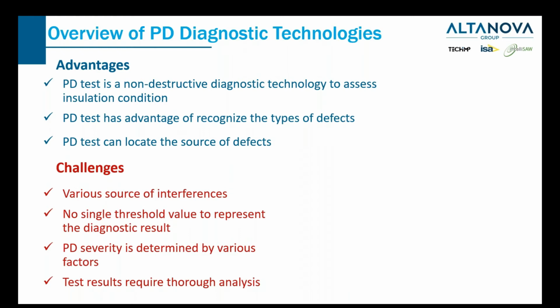In contrast, the cavity discharge is within the organic insulation material. Even if we have only tens of picocoulombs of cavity discharge, it's still very dangerous to the insulation system. So that explains why we cannot just use a magnitude to judge whether the equipment is good or bad.